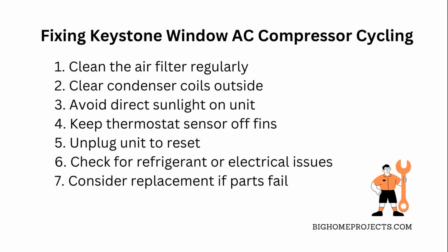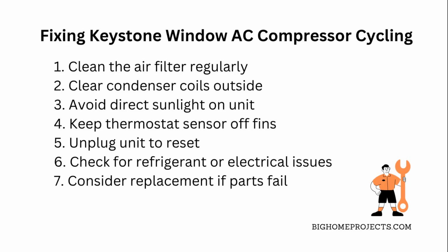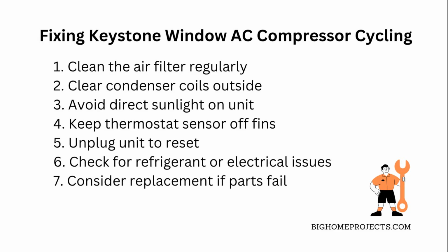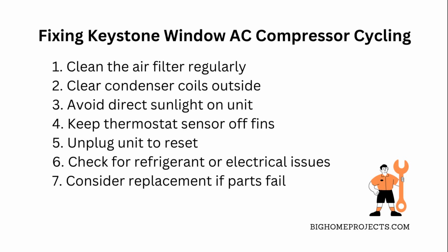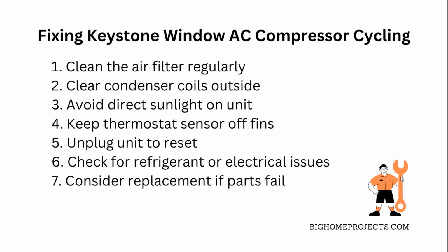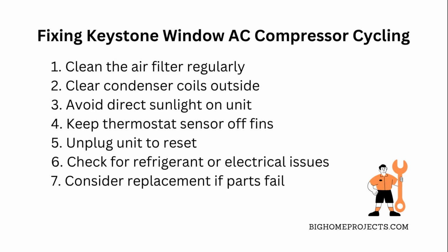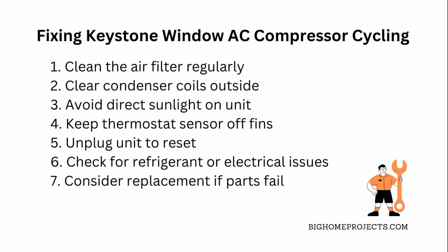Next, check if the condenser coils outside are clogged with dirt or debris. If they are, gently clean them with a brush or hose when the unit is off. Also, inspect the unit's placement. If it's in direct sunlight all day or too close to walls, it might overheat and shut off to protect itself. Another thing to look at is whether the thermostat sensor inside the unit is touching the cooling fins. If so, it can misread the temperature and cause short cycling.